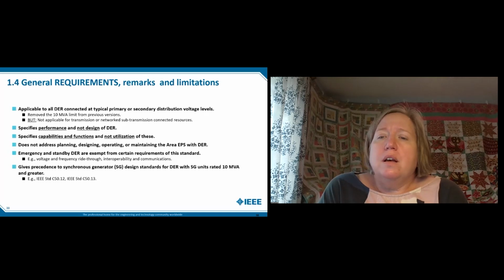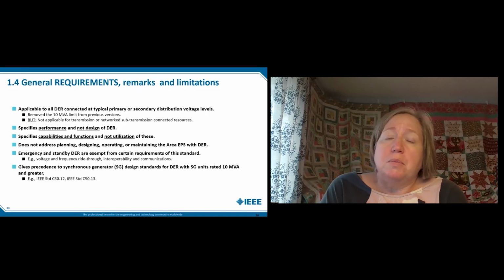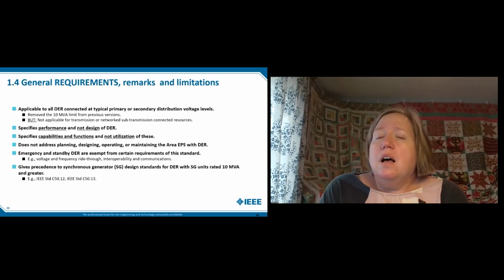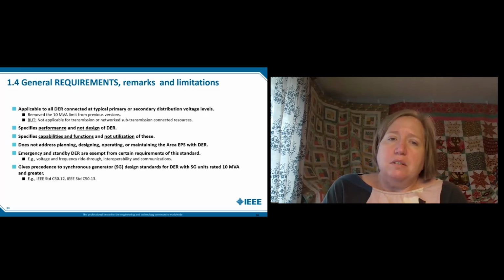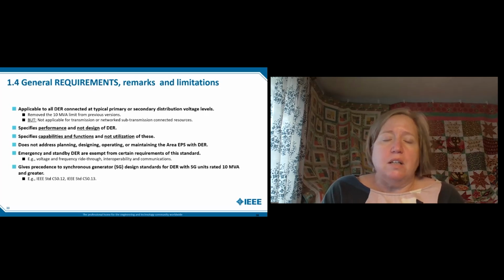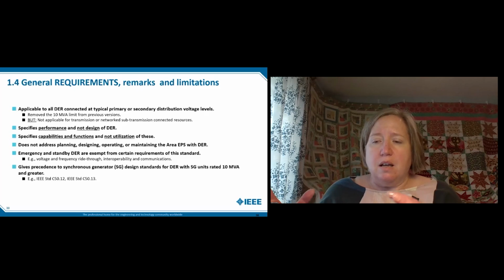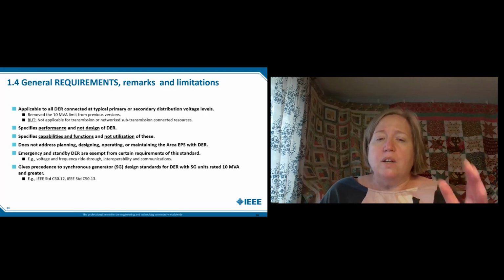So the first thing that we did was we removed the 10 MVA MW limit from the previous version. And we continued that this is not applicable to interconnections on the transmission or network sub-transmission resources. The important thing is this is the performance of the DER, not the design of the DER. It's specifying the capabilities and functions, but not the utilization of the DER. So the DER can do all this stuff. It's up to the area EPS or the authority governing interconnection requirements, the AGIR, to decide what you're going to use.